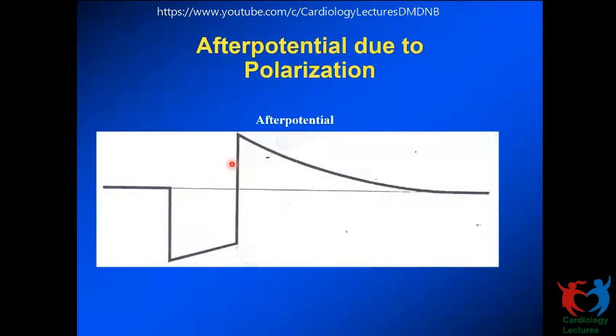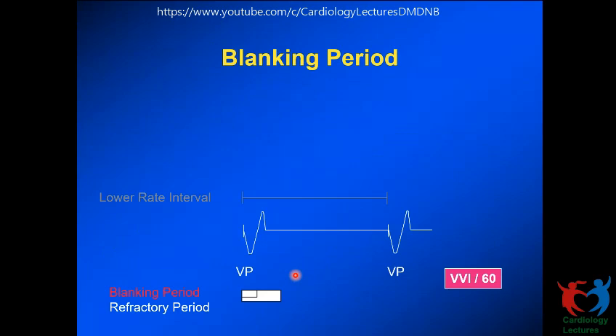And that's not all. When we deliver a pacing pulse, we talked about polarization, which means we are delivering electrons. There's an accumulation of electrons, which is of a good amplitude at that point of time. And after we stop the pacing pulse at the end of the pacing pulse duration, this slowly dissipates. Though this is a highly powerful, noisy time at voltage amplitudes. But as we said, the pacemaker sensing circuitry is designed for millivolt amplitude. We don't want the pacemaker sensing circuitry to get damaged. So that's why the initial portion after the pacing event inside the refractory period is a blanking period where the pacemaker senses nothing. So that's a totally blank period. It does not even sense that.